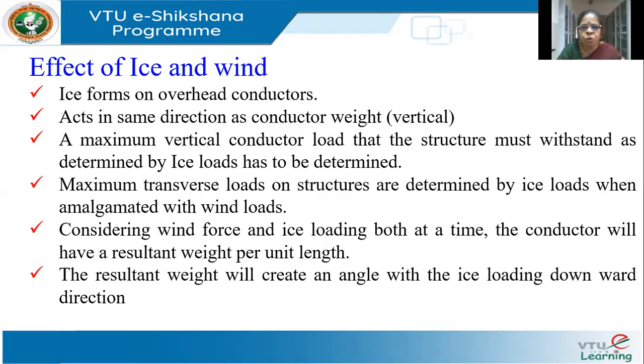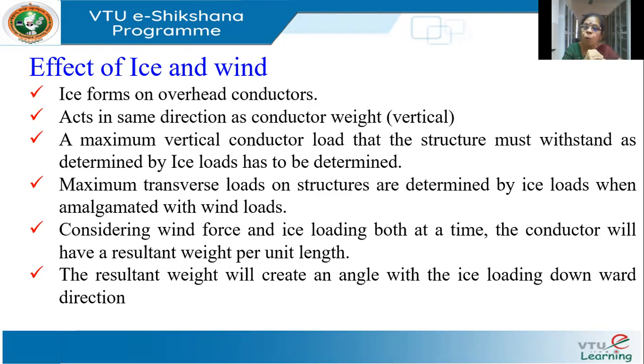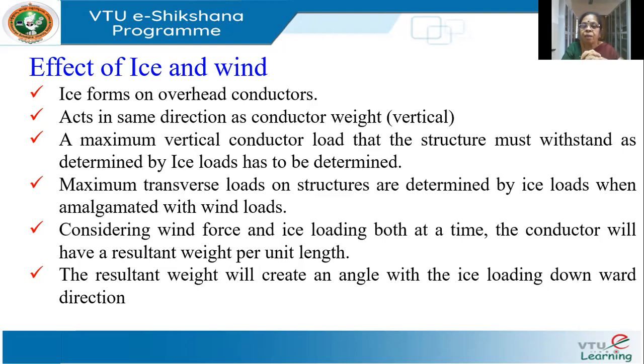Ice, snow, hail, storm — all these different forms of ice form on overhead conductors. Ice acts in the same vertical direction as the conductor weight because it is deposited on the conductor. We have to determine the vertical load the structure must withstand when there is ice. Ice is considered as a load because it increases the weight. We also determine the maximum transverse loads on structures due to ice loads, and integrate them with wind loads. We will now see how the conductor weight per unit length changes.